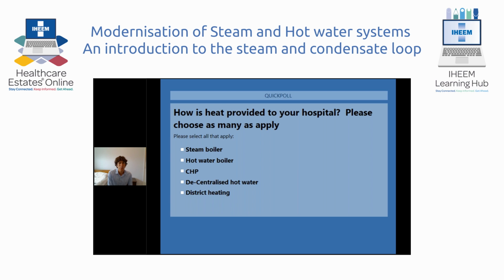Typically, we're burning hydrocarbons, and primarily in the UK, it's natural gas. The flue gas temperature is both hot, typically between 180 and 200 degrees C, depending on the steam pressure we're using, but also humid. When we burn natural gas, it's CH4, and the products of combustion are CO2 and H2O. The H2O is water vapor going up the stack. I'll talk more about that later.